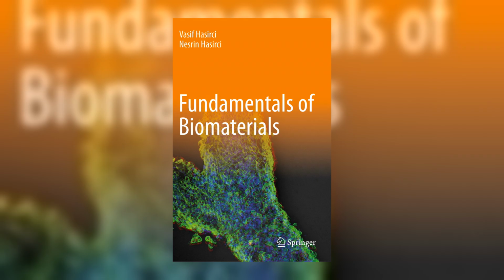This section explains how cytotoxicity is screened in vitro before any animal ever sees the material. Toxicity gets screened first by interposing a confluent lawn of standardized fibroblasts, the L929 line and its cousins, between the device and the organism, then challenging it two ways. The first way is direct. The material sits on the cells. The second is indirect. Only its extract does.